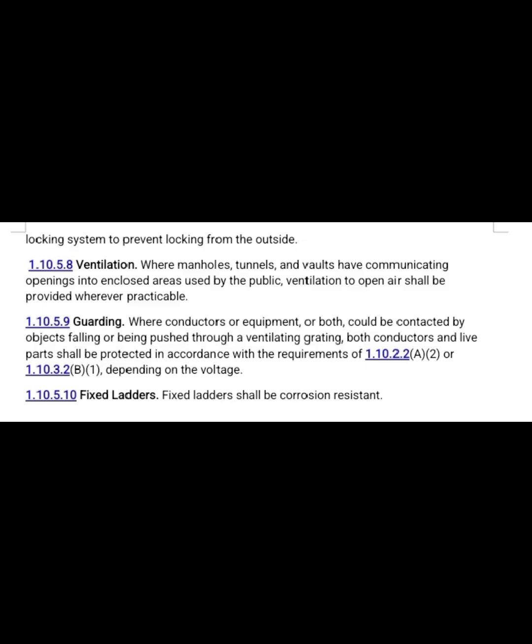1.10.5.8 Ventilation. Where manholes, tunnels, and vaults have communicating openings into enclosed areas used by the public, ventilation to open air shall be provided wherever practicable. 1.10.5.9 Guarding. Where conductors or equipment or both could be contacted by objects falling or being pushed through a ventilating grating, both conductors and live parts shall be protected in accordance with the requirements of 1.10.2.2 A2, or 1.10.3.2 B1, depending on the voltage. 1.10.5.10 Fixed ladders. Fixed ladders shall be corrosion resistant.